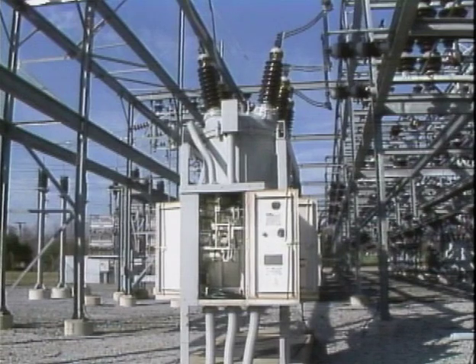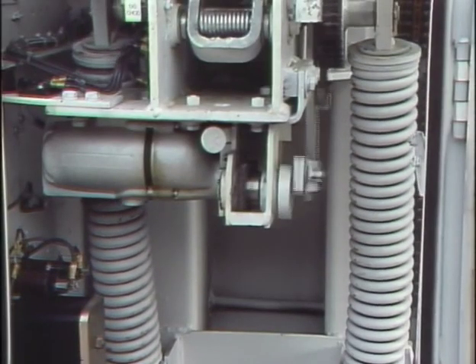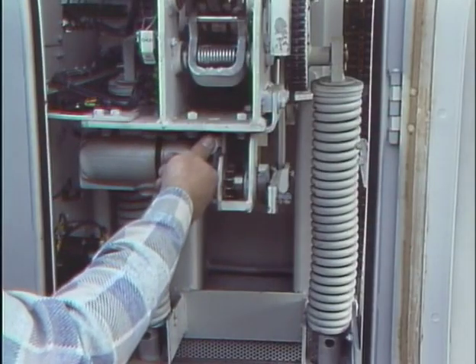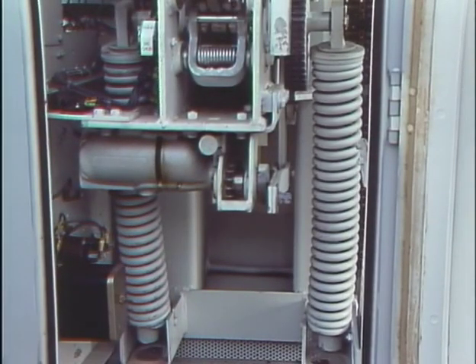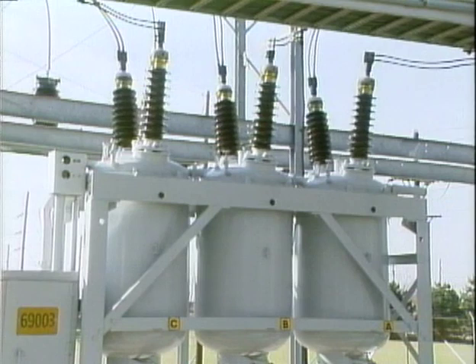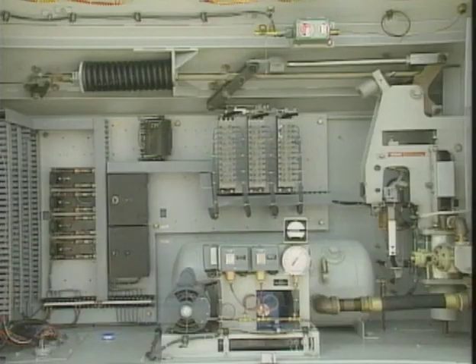A second type of circuit breaker operating mechanism is the motor spring mechanism. With this type of mechanism, a motor operates to compress or charge closing springs. The closing springs provide the force needed to close the breaker contacts and at the same time compress or charge an opening spring. In this example, the opening spring is enclosed in a cover pipe near the top of the breaker. The spring is connected to the breaker contacts and the motor spring operating mechanism by operating rods. It provides the force needed to open the breaker contacts. A third type of operating mechanism is the pneumatic mechanism.